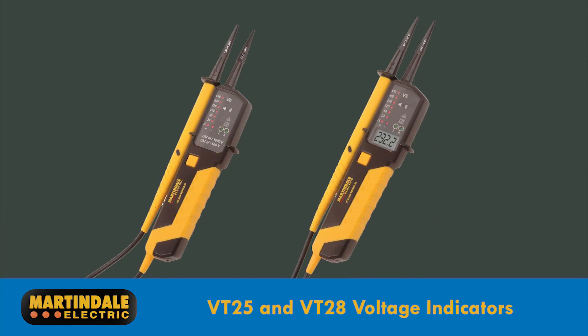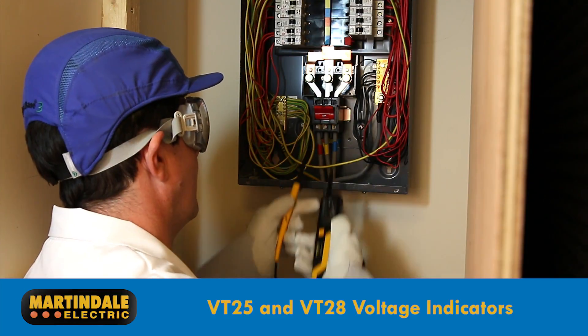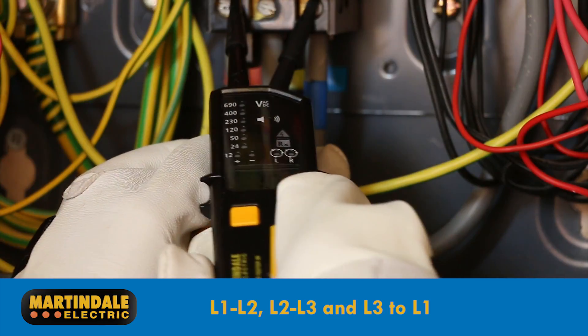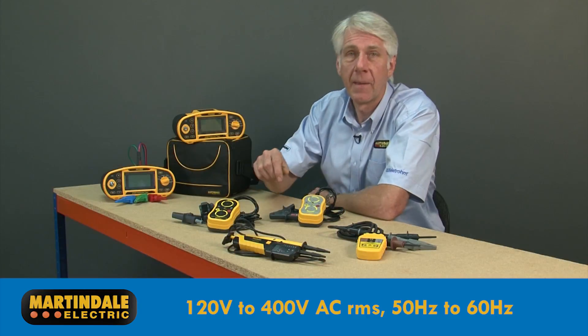Another solution are the VT25 and VT28 voltage indicators. Because these are two-pole testers, the phase-to-phase voltage and direction of rotation will have to be taken between each phase in turn — L1 to L2, L2 to L3, and then L3 to L1. They operate between 120 and 400 volts AC RMS for 50 to 60Hz supplies. So we can see that Martindale have some great solutions for the verification of phase rotation.